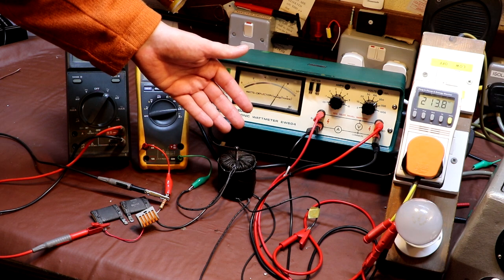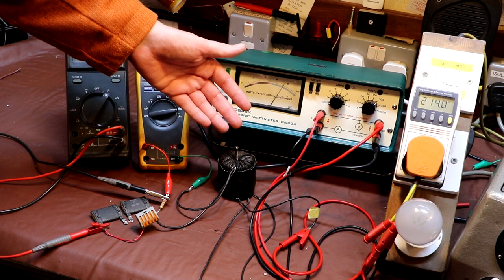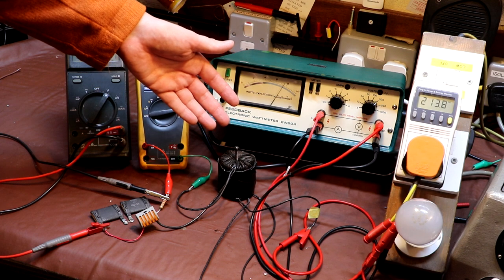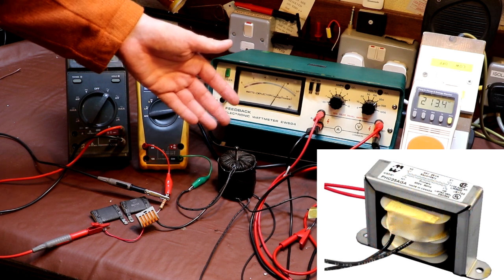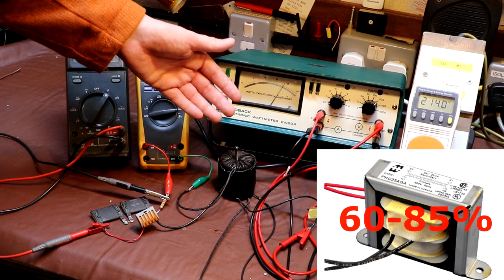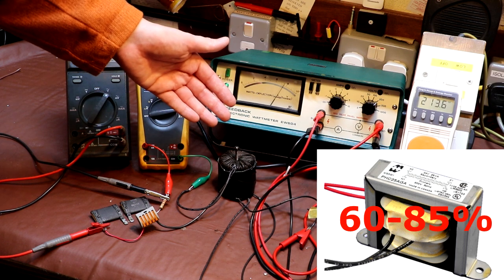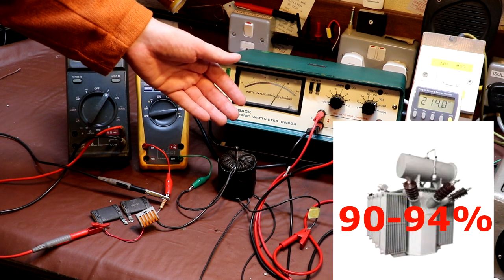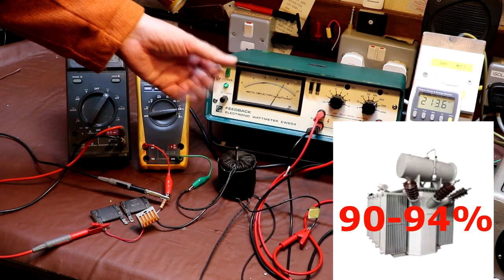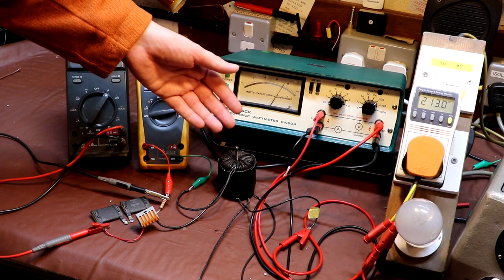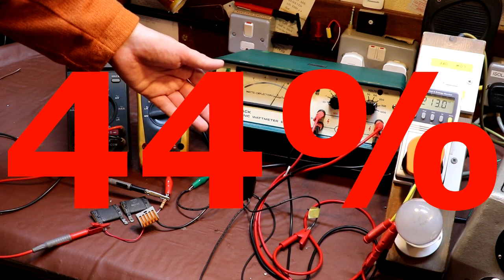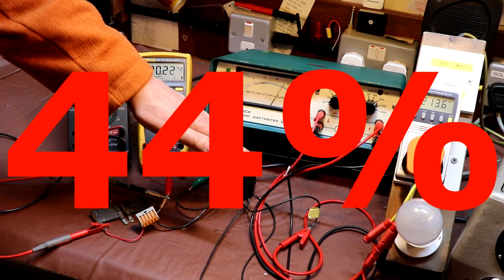to transformers. As it turns out, the efficiency of a transformer actually increases with scale. So small transformers like this are usually relatively inefficient, but we would probably still expect a modern transformer, even a small one, to achieve better than 60% efficiency. A large transformer could be between 90 and 94% efficient, but a small transformer like this may be 60% efficient, and we're considerably below that. We're only at 44% efficiency, and I'm not surprised because this transformer is getting quite warm to the touch.